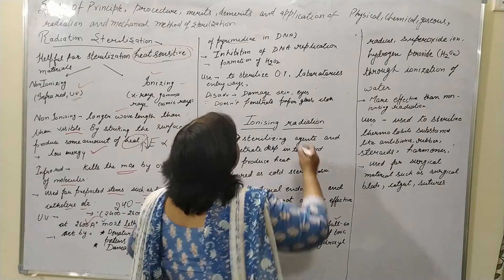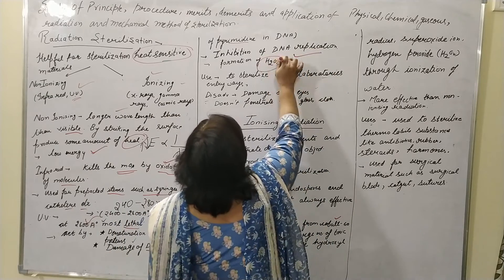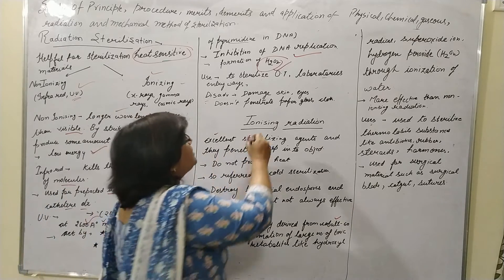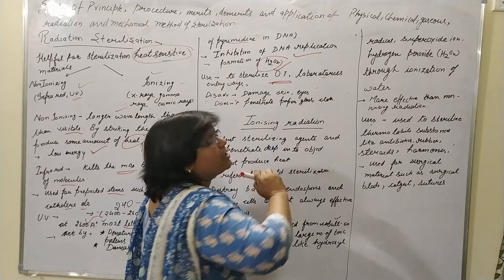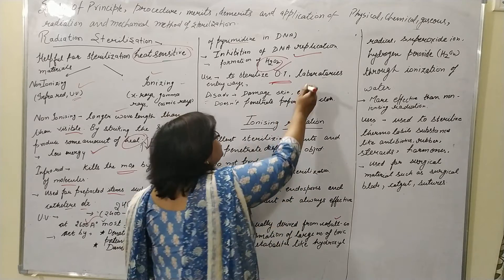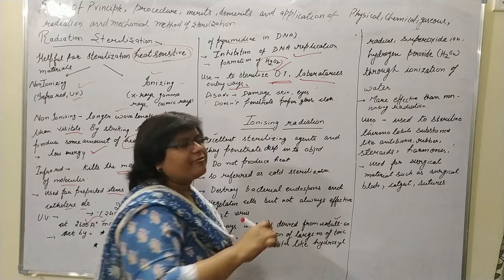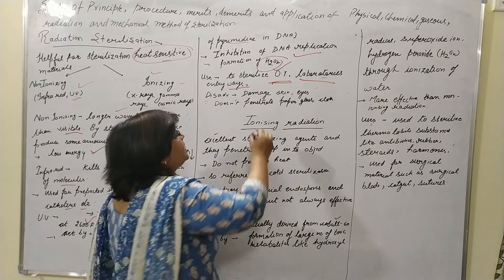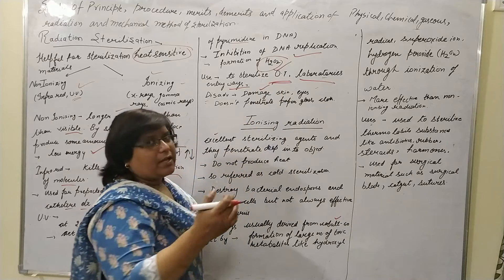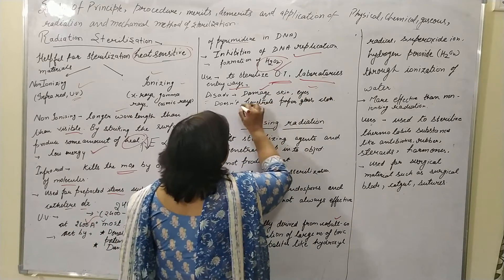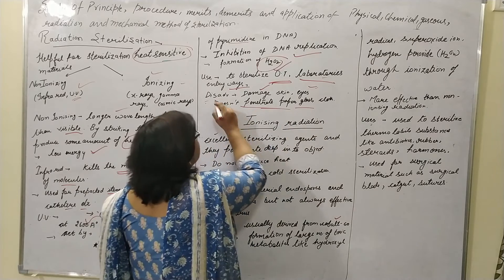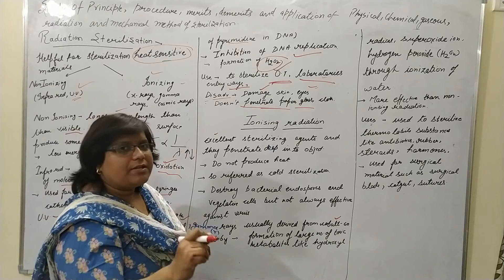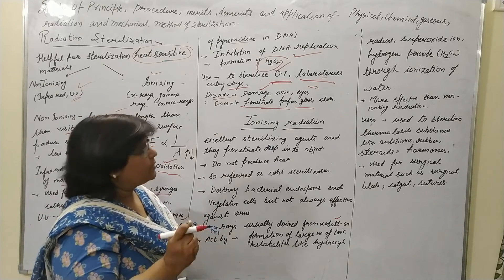UV also inhibits the DNA replication process and forms hydrogen peroxide. It is used to sterilize the OT (operation theatre), laboratories, and different kinds of entryways. However, the disadvantage is that it damages the skin and eyes, and it does not penetrate glass, paper, or cloth.